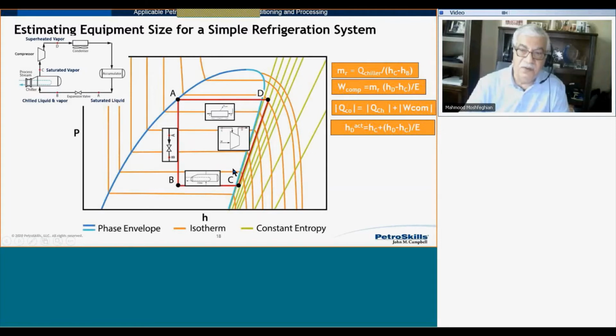I know my chiller duty. So I divide the chiller duty, as you can see here, by... the system is a closed loop, so the mass flow rate is the same through every component. It's Q of the chiller divided by HC minus HB, which is the enthalpy change. That gives the mass flow rate through the system. Then the power requirement is mass flow rate times HD, enthalpy at point D isentropic, minus HC, and then to make it actual, I divide it by the efficiency of my compressor, which I get from the vendor. So that gives me my actual power.